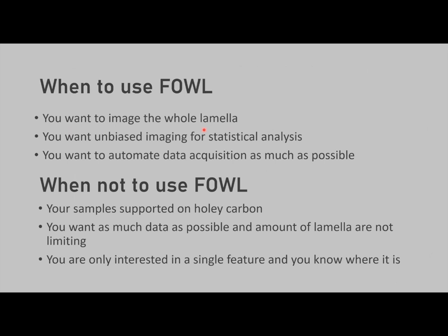I think it's also important if you want unbiased imaging of your lamella, so you don't get some inherent bias where you image certain features more often than they actually appear. And it's also great if you want to fully automate your data acquisition, because you no longer have to choose sites and think about where to focus. You just point at the lamella and the thing goes. And even if, due to the tilt, contaminations come into view, it will still image all of it.